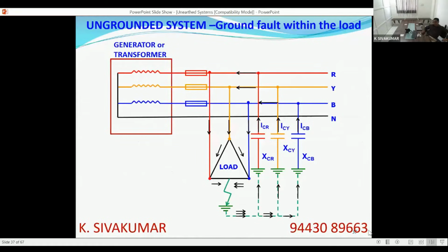This is a network, there is a source and there is a load. If you can see, the one winding of the load has got an earth fault. You can see the direction in which the current flows. There will be ICR, ICY, ICB and through the load, there will be current flow. The capacitors will charge and discharge through the load. Capacitors will feed into the fault through the load now.